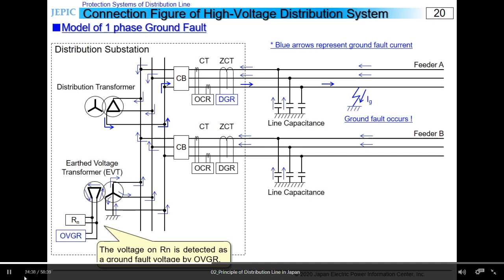The directions of the fault current, so to speak zero-phase current, are different between feeder A and B at the DGR point. The earthed voltage transformer, which is installed to each distribution transformer, measures the ground fault voltage. Some of the ground fault current flows through the earthed voltage transformer, and the voltage caused by this current is the voltage of resistance Rn put in the secondary side of open delta. And this voltage applied to Rn is detected as a ground fault voltage.